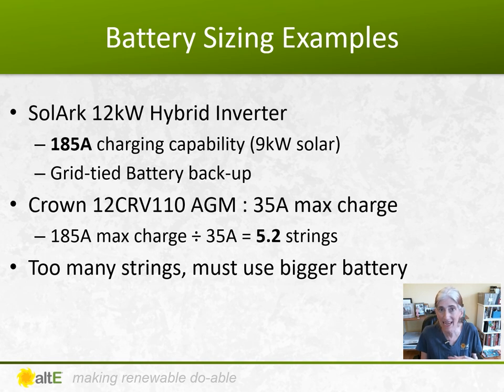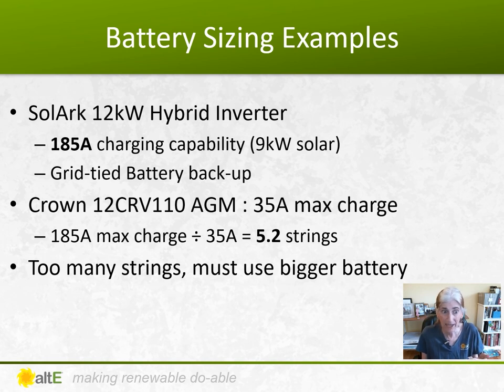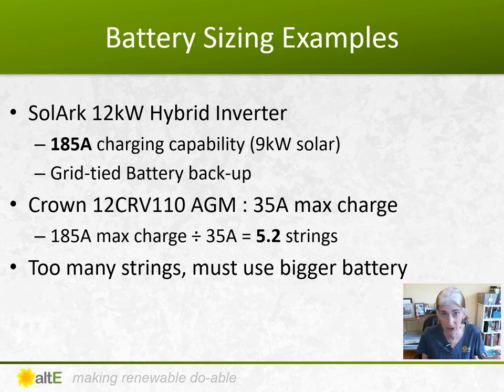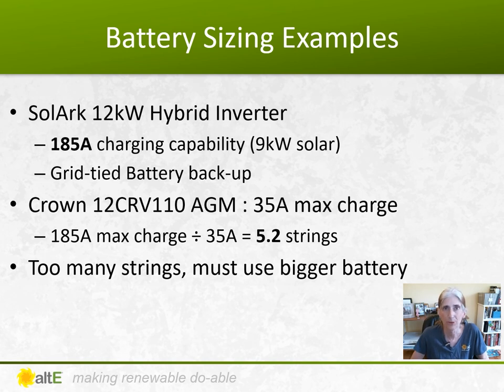Starting with the Crown 110 amp hour sealed battery, which has a 35 amp maximum charge rate: taking 185 amps of solar with a 35 amp maximum per battery, you'd need over five strings — basically six parallel strings. But Crown doesn't recommend using six parallel strings; they recommend only two. So you cannot use this battery in this design and have to start again with a different battery.